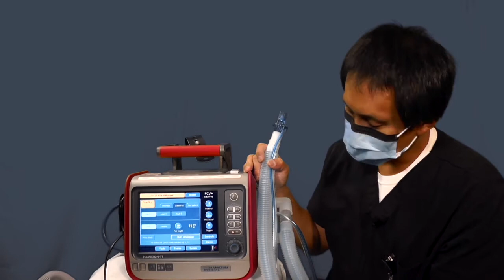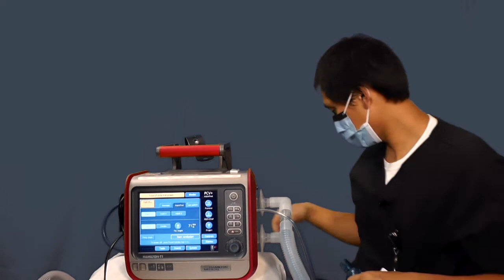So once you get your settings in place that you want, you can go ahead and start the ventilator. To start this machine, all you have to do is hit the start ventilation button. And it powers on. It'll give you a 1 minute grace period of silence while it's turning on and getting used to the patient.